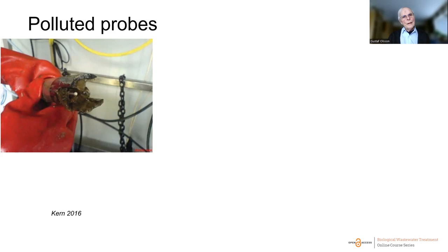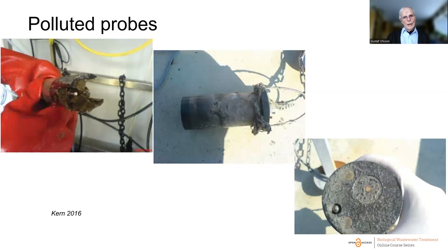However, the environment is hostile, and the probes are certainly not clean as they would be in a laboratory — they are affected by the environment. This has to be considered so that probes are properly cleaned. Some probes have a degree of self-cleaning, but the operator and instrumentation engineer really have to watch out for the hostile environment all the time. You simply cannot leave the instruments for a long period and trust the data.